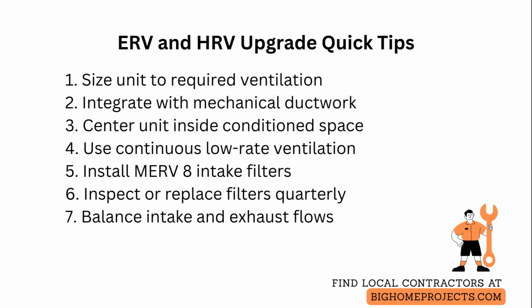A common method is to use the local mechanical code or a guideline of fresh air per person plus a fraction of air per square foot to get a target cubic feet per minute, and then select a unit rated for that flow at installed duct static pressure. Integrate the unit with the mechanical system so supply and exhaust connect to the return and outside ducts in a way that minimizes pressure imbalances.